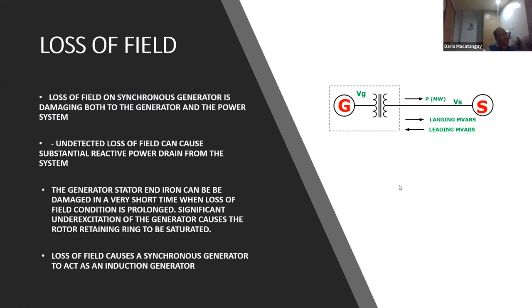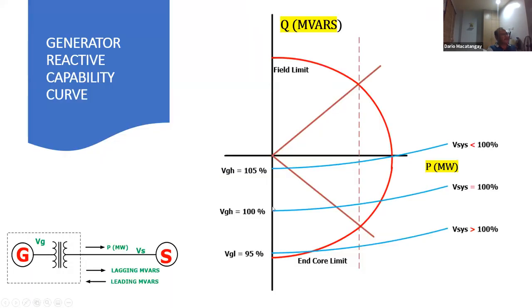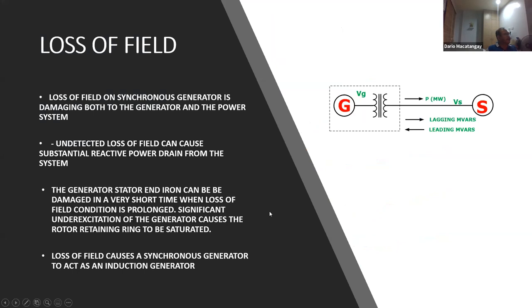Loss of field protection detects the loss of excitation. When it detects a loss of the excitation, that means that you're operating down here, right? Because the characteristic of loss of field is over here. Loss of field on a synchronous generator is damaging both to the generator and the power system. Undetected loss of field can cause substantial reactive power drain from the system.